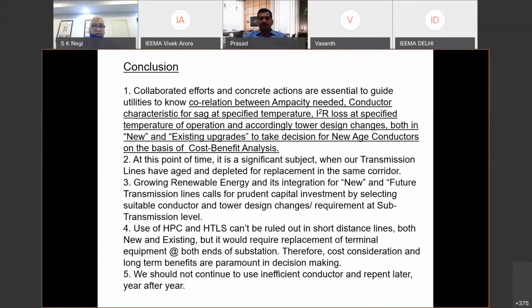and use the cost analysis to satisfy the decision maker for the usage of a new conductor. At this point of time, it is a significant subject when transmission lines have aged and depleted, for the replacement in the same corridor. Now, 400 kV lines were built from 1978 onwards, and I am very sure that many coastal areas and other places will need this replacement. We have found this particular problem in coastal areas, and we have been replacing those conductors. I am very sure these transmission lines, which are 34-40 years old, will also age and require replacement. At this point of time, it is very significant that in the same corridor, in the same tower or a different tower, we use these new age conductors.